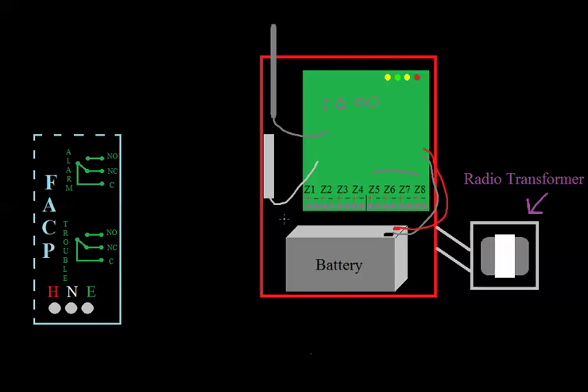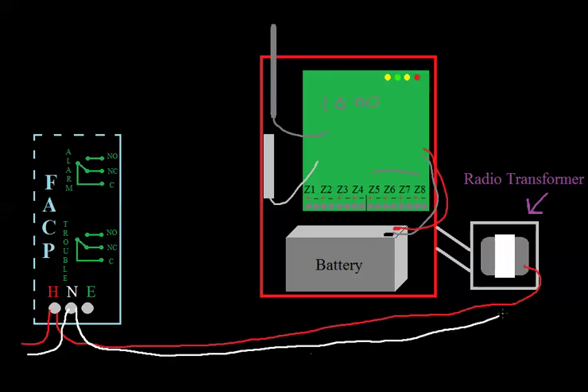So, well, first of all, we need to power the radio up. So you can see this battery in here. There's a backup battery, and then there's a transformer. So the fire alarm panel takes 120 volts. That's something we haven't talked about yet, but it's simple enough. So usually you use the same circuit the fire alarm is using. You take your hot circuit, go to the transformer, take your neutral, go to the transformer, and that steps it down.